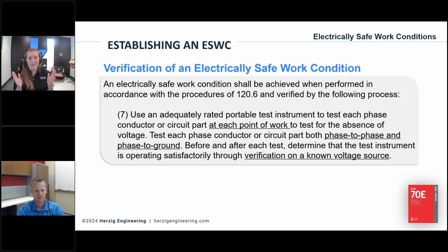Qualified and authorized are two separate terms. There's authorized personnel for lockout tagout, and then there's qualified personnel for electrical work. Not all authorized personnel are qualified, but all qualified personnel need to be authorized because they have to be able to establish an electrically safe work condition. Part of that's lockout tagout. The difference is someone who's authorized but not qualified can't do step 7. All that to say, it has to be a qualified person in order to do step 7 here. That's where that splits off.